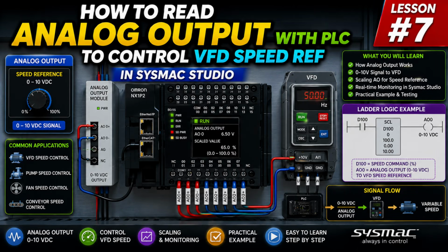In today's session, we are going to see how we can generate analog outputs using Omron PLC. Let's suppose we have a VFD and we want to control the motor speed. VFDs control the motor speed using the speed reference signals coming from the PLC. Mostly these signals are analog 0 to 10 volts or 4 to 20 milliamps. In most of the cases, 0 volt speed reference signal means 0 hertz and 10 volts speed reference means 50 hertz speed. Now let's see how to implement this.